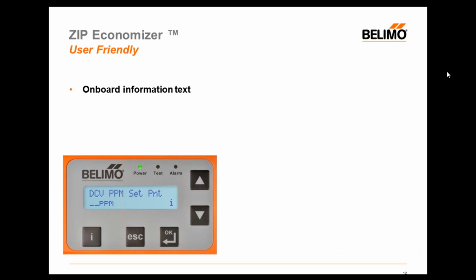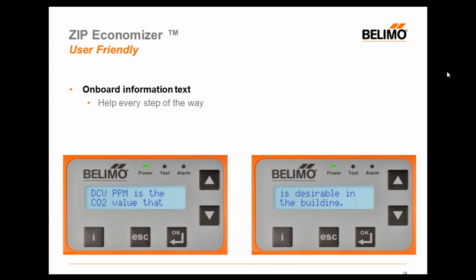We tried keeping it simple by providing an onboard help in setting up and troubleshooting the economizer. There's a little I button there on the menu screen, and if you push the I button, you get more information. As previously mentioned, the old economizers are difficult to troubleshoot, and you really had to be present to see what the problem was. With up to 10 historic alarms, alarm counters, and timestamps, it's really easy with the ZIP economizer.